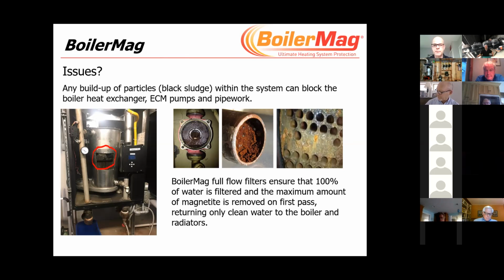So the BoilerMag is a magnetic filter that we install in line, taking the full flow of the filter, preferably, to make sure we filter out all that magnetite on the first pass, making sure only clean water returns back to the boiler or the radiator or whatever it is you're trying to protect. There's a few pictures there that I'm sure the guys out in the field on installations will recognize.